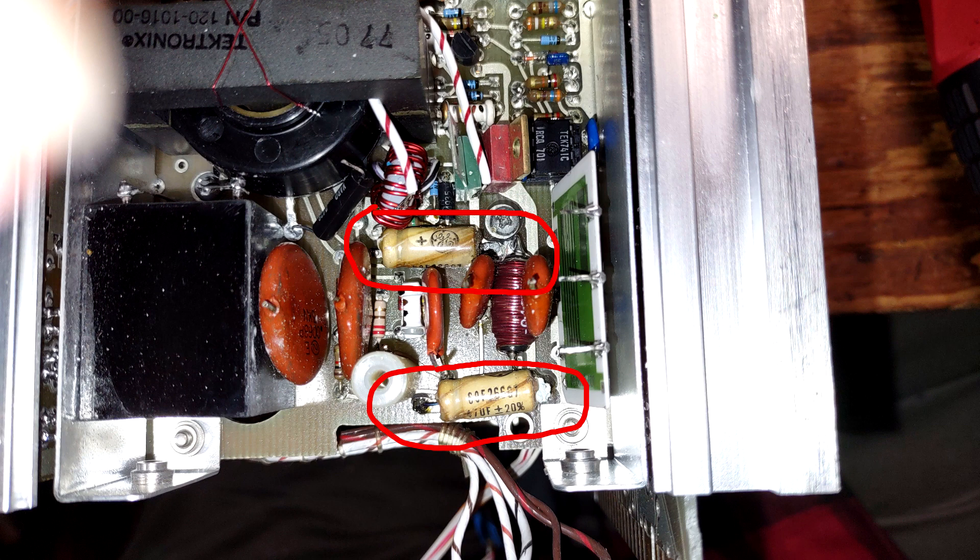Failure of these capacitors, which are tantalums, is common in this instrument. As can be seen in this photo, both caps have started to leak electrolyte onto the circuit board.